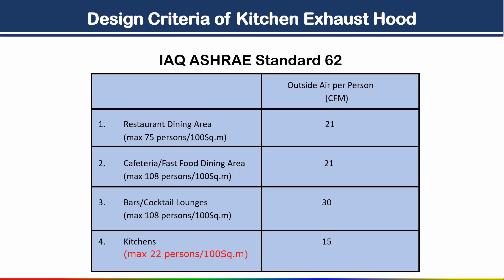In this table you can see indoor air quality requirements as per ASHRAE standard 62. For a restaurant dining area, for 100 square meters the maximum occupancy is 75 persons, and outside air per person is 21 cfm. For a cafeteria it is also 21 cfm. For a bar or cocktail lounge it is 30 cfm. For a kitchen, maximum 22 persons occupancy per 100 square meters, and outside air per person is 15 cfm.